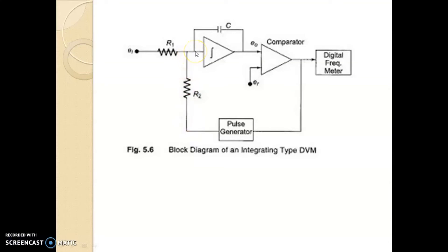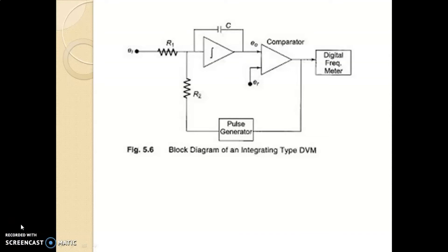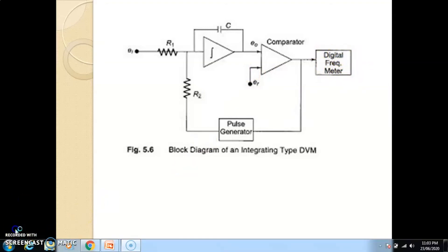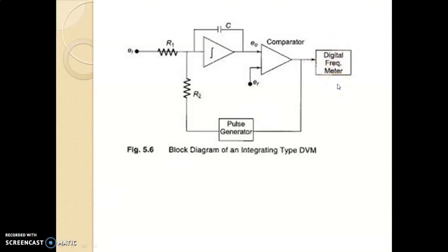As the comparator continuously changes state, the pulse generator generates pulses at a regular interval. These generated pulses at a regular interval are always proportional to the input voltage applied to the integrator. This pulse frequency signal is proportional to the input voltage, and the pulses are counted using a digital frequency meter and calibrated in terms of input voltage.